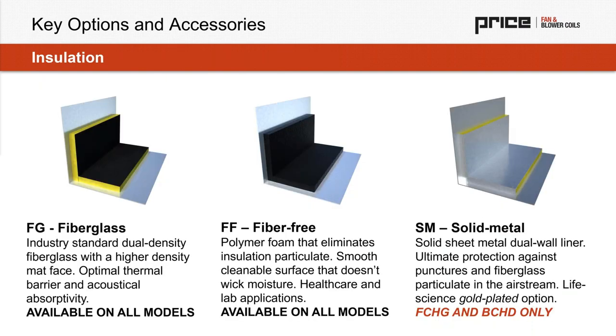Other things to note for these products: one key optional accessory choice is insulation. As a high level rule of thumb, some guidance from the manufacturer, we might say fiberglass for acoustics is best. Whenever you can manage to use fiberglass liner, you're generally going to yield the quietest room for most applications. It is extremely acoustically absorptive. It really helps reduce duct noise and manages radiated noise very well too.